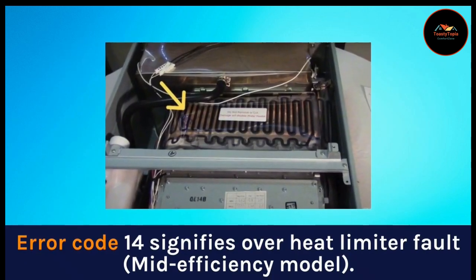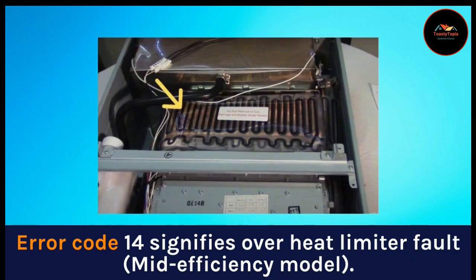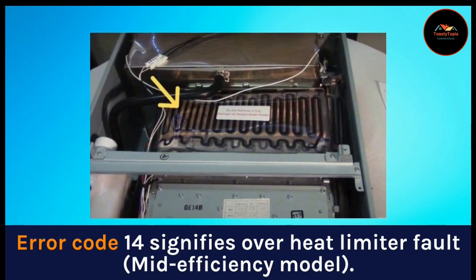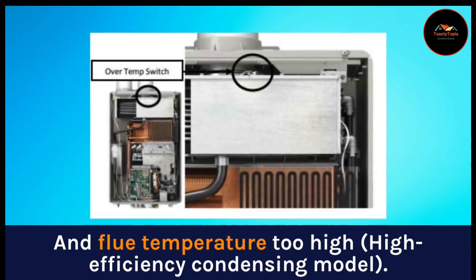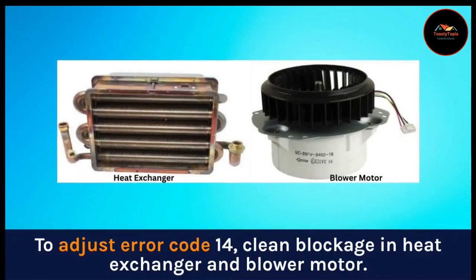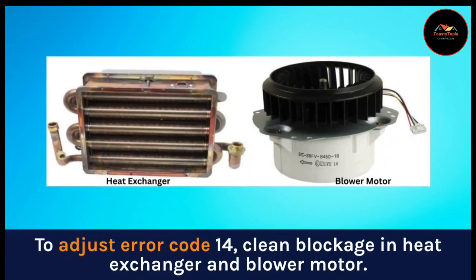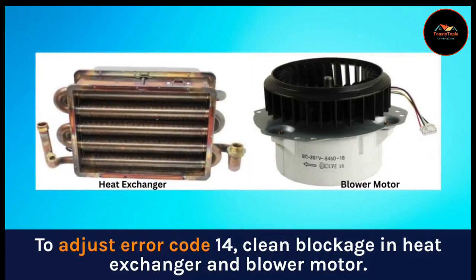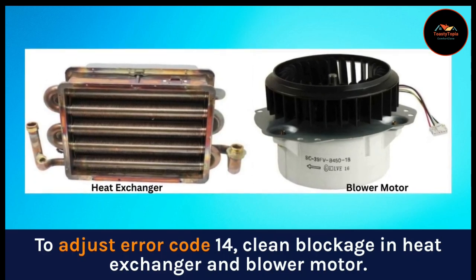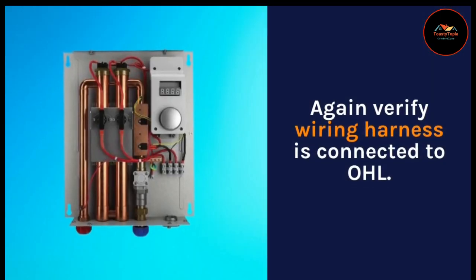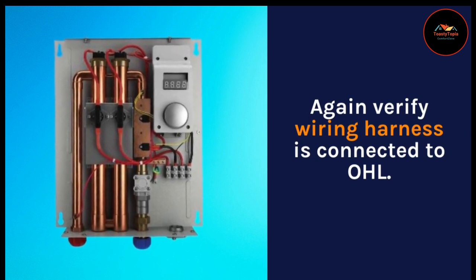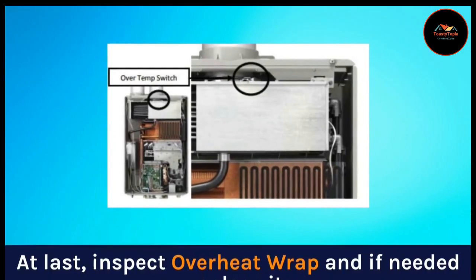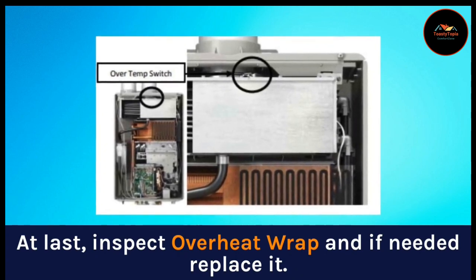Error code 14 signifies overheat limiter fault on the mid-efficiency model, and flue temperature too high on the high-efficiency condensing model. To address error code 14, clean blockages in the heat exchanger and blower motor. Verify the wiring harness is connected to the OHL. Inspect the overheat wrap and replace it if needed.